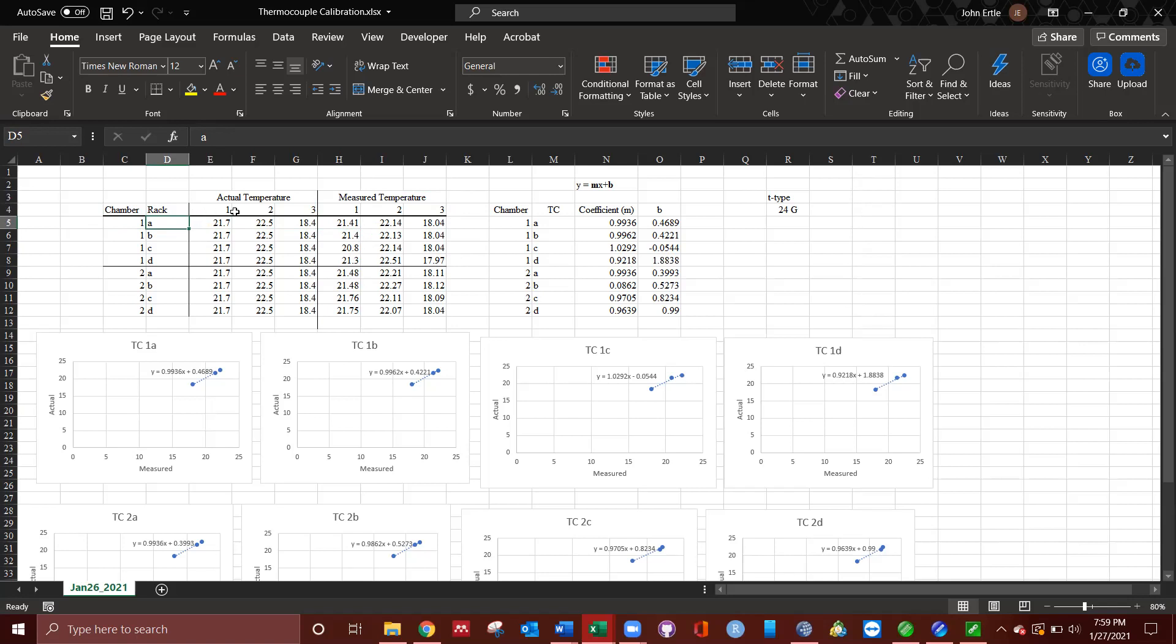What I've done is I've selected three temperatures to calibrate towards. You really only need two, but since my temperature is going to be ranging from 19 to 23 degrees Celsius, I've picked temperatures within that range, towards the top end of that range and towards the bottom end of that range, even below it. This means I'm going to be able to calibrate rather precisely towards the temperature range that I am looking to have the thermocouples measure reliably. If I was calibrating at near zero degrees Celsius and then like one at 23, that's not going to give me a very precise measurement for the range that I am expecting these thermocouples to be measuring.